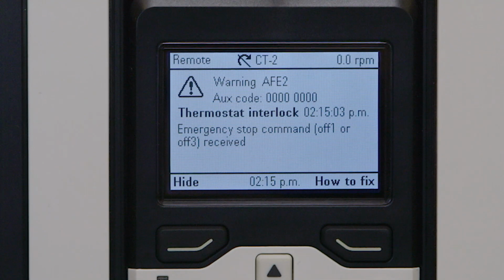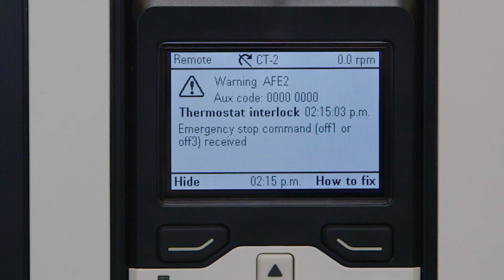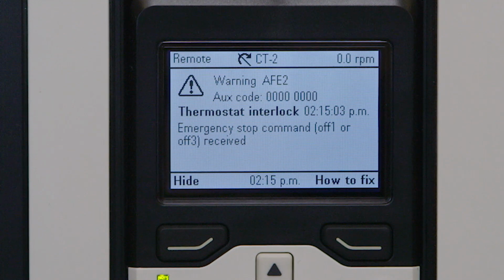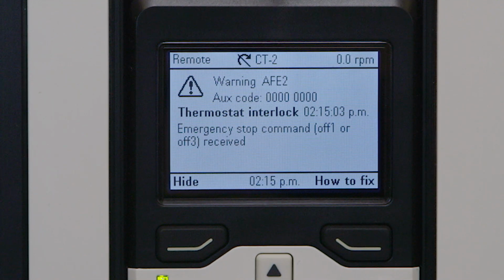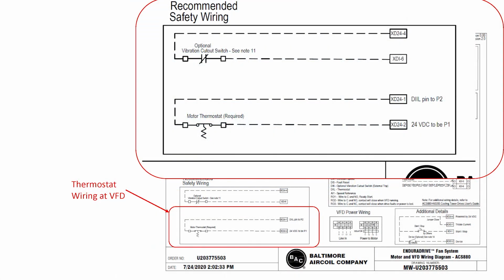The motor has built-in thermostat switches that will prevent operation if the motor gets too hot. You will see the warning thermostat interlock if the motor gets too hot. You will also get the same thermostat interlock warning if the wires from the motor to the thermostat are not correctly landed on the VFD. In either case, operation of the motor is not possible while this warning is active.